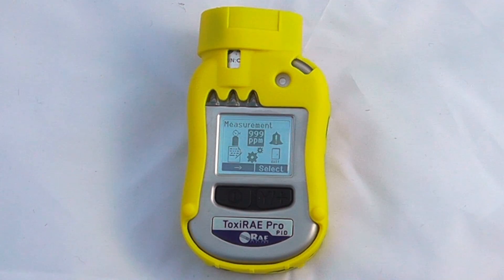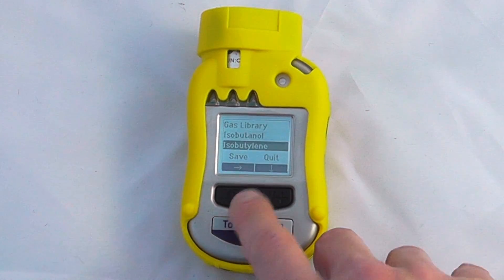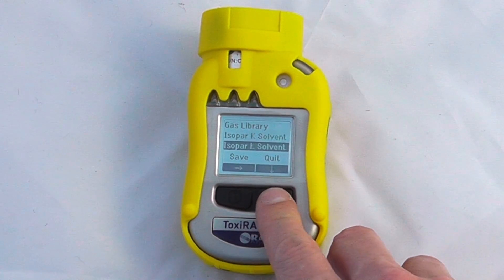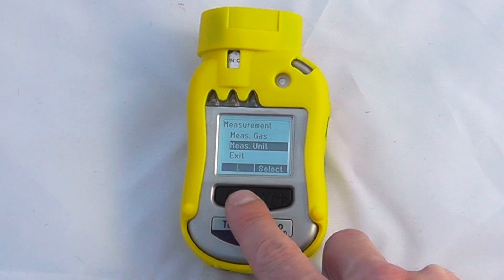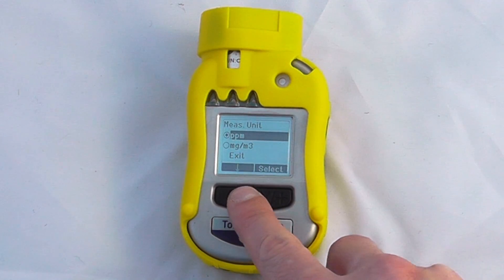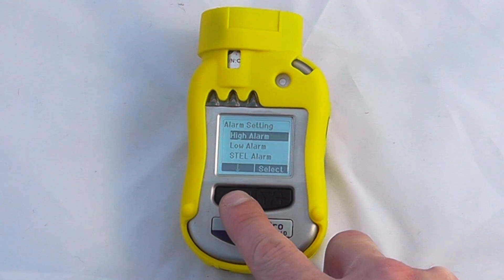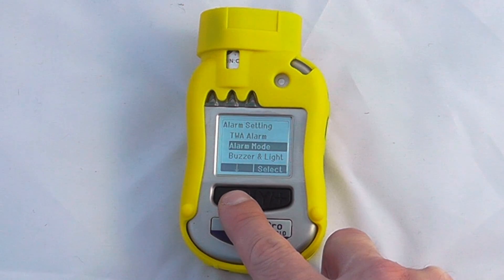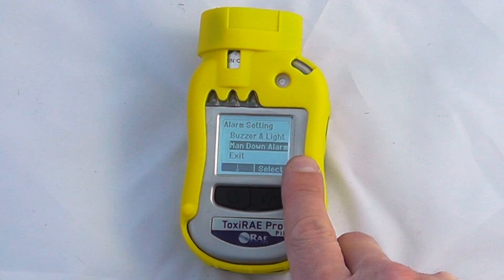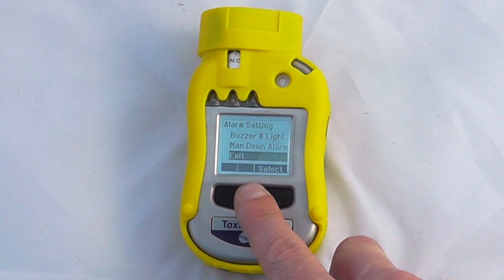We can exit the calibration menu and look at measurement menus. In terms of measurements, we can change our measurement gases using preset correction factors for whatever gas is in the library — this can also be done more quickly through the software. We can change the measurement units between parts per million or milligrams per cubic metre. Alarm settings cover high alarm, low alarm, STEL alarm, and TWA alarm. Alarm mode lets you choose between a latched alarm or a standard safety alarm, plus buzzer and light settings. This unit also has a man-down feature, much like the MultiRAE.